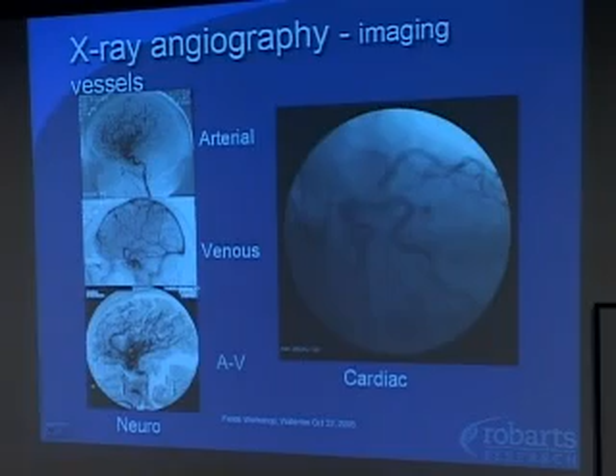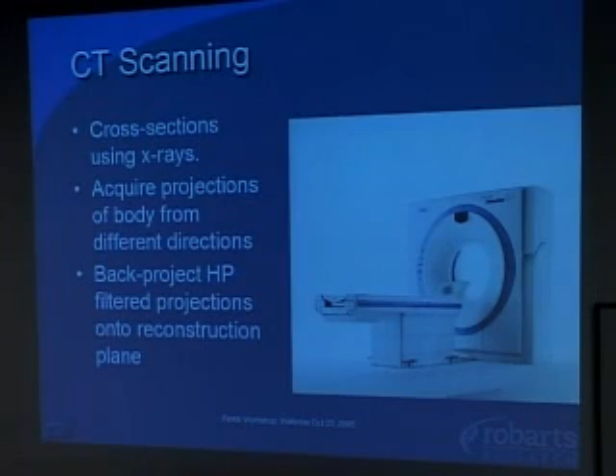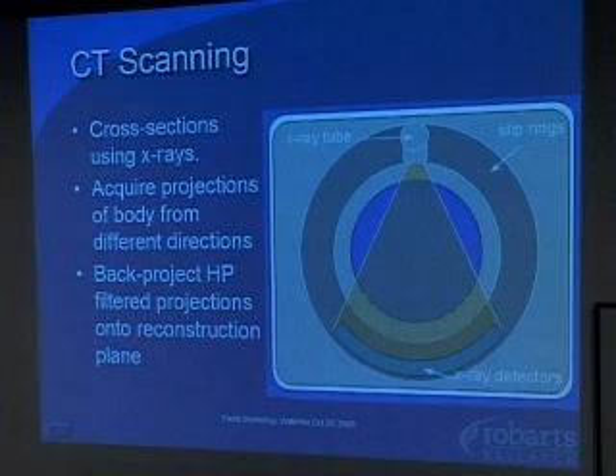Of course, we're all familiar with today's state-of-the-art CT scanners. Instead of giving you projections of objects, they give you cross-sections of objects. And as I mentioned, if we can record projections of slices or volumes from many, many directions, we can mathematically reconstruct them to form a 3-dimensional image. Inside a CT scanner, we have a source, an X-ray tube that rotates around sometimes up to 3 times a second, and an array of detectors. Historically, this was a single array of 1,000 to 2,000 detectors. Now it's up to 64 of these arrays stacked side by side, so that you can scan a slab with 64 slices in it, that thick, in less than half a second. And so by spiraling this through, you can record large chunks of the body in just a few seconds.